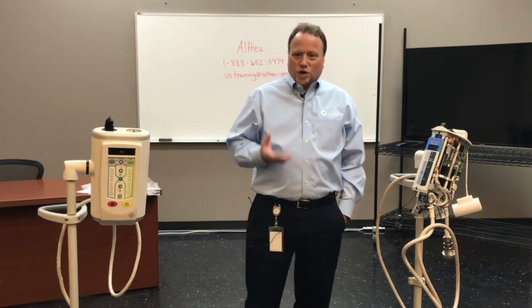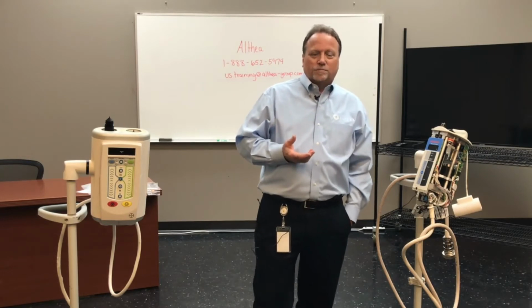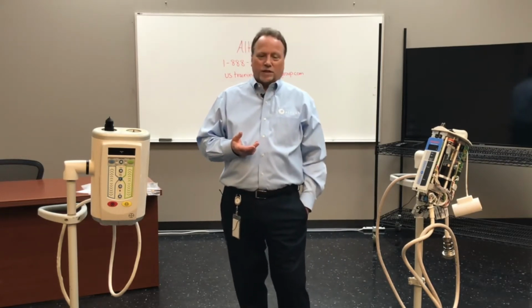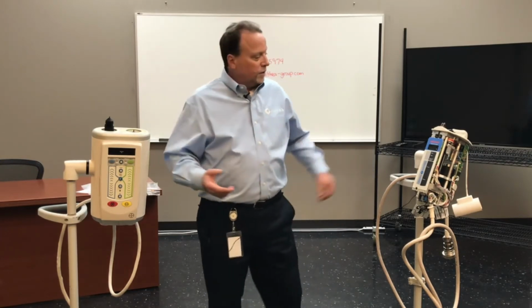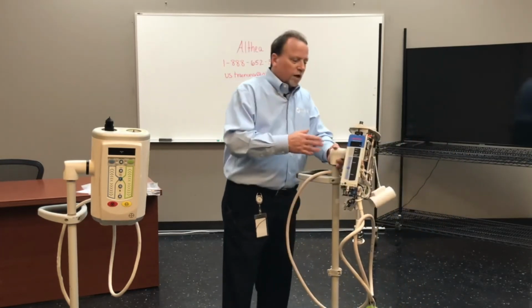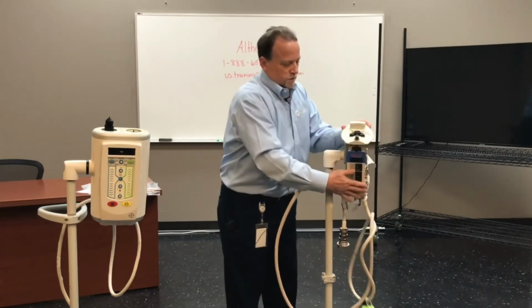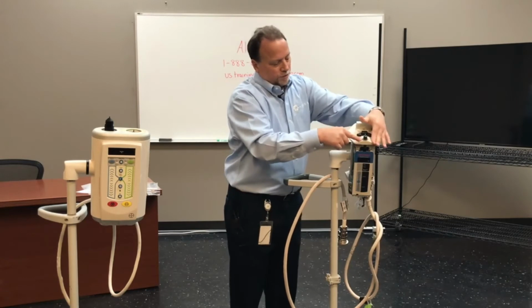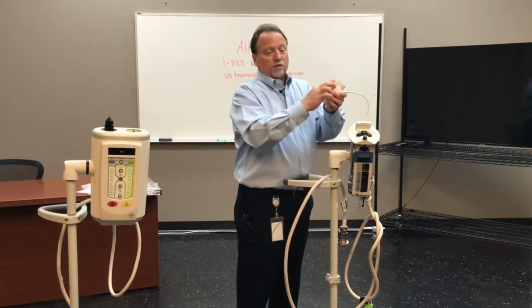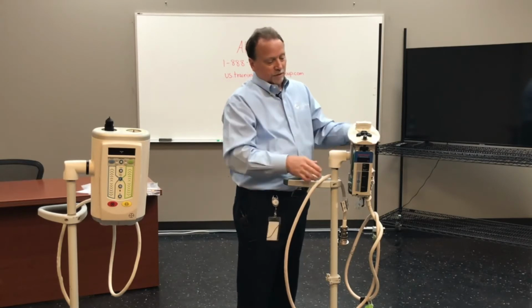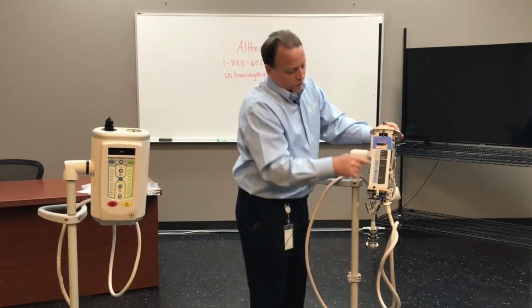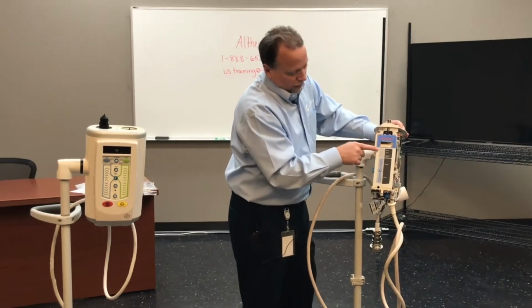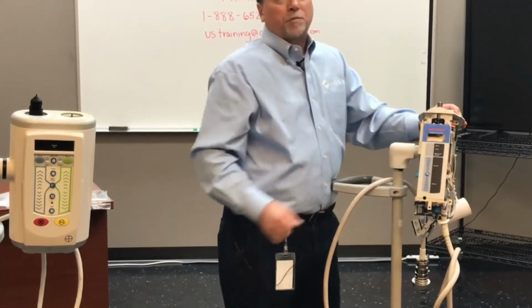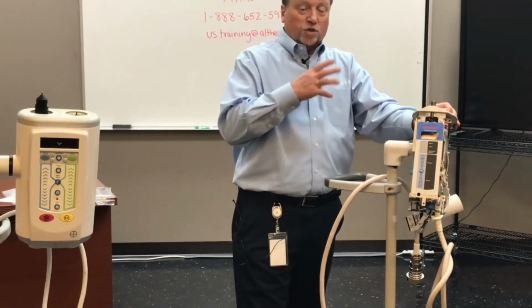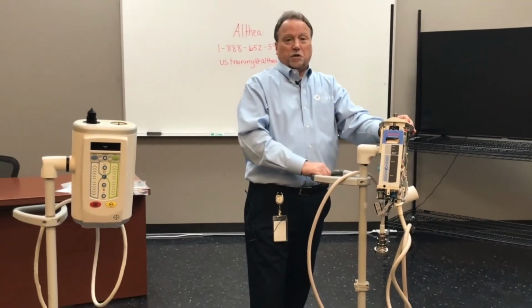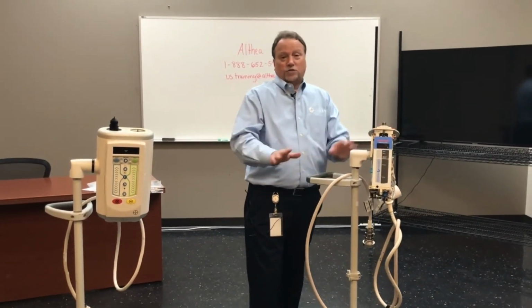Cleaning will take the longest during a PM. I can spend an hour and 15 minutes cleaning the injector. You'll be taking the covers off, like on this Provis. You're going to have contrast up in here, around here, through here. The warmer, you'll have contrast dripping down here on the sides. The overlay here, you can actually see a little bit of it around. You'll have contrast in here. You may not even be able to take the front cover off because the contrast is acting like glue. It's just plain terrible. I can't stress it enough.